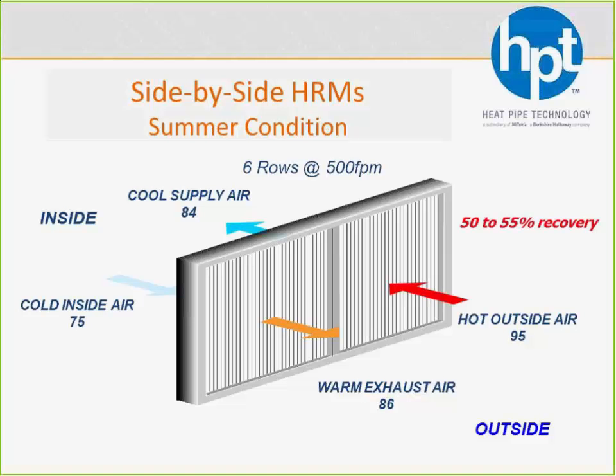We are a sensible only heat recovery device, which means that we only work with delta T's. So we're going to be at 6 rows, about 55% effective, which means that whatever that total delta T is, if it's 75 exhaust, 95 outside, that's a 20-degree delta T, we're going to recover about 55% of that temperature. So we're going to pre-cool that 95-degree air by about 11 degrees and cool it down to 84 degrees so the cooling coil doesn't have to work as hard.